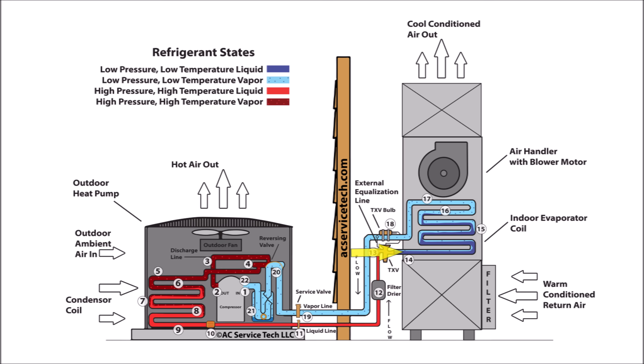At step fourteen, the liquid exits the metering device as a low pressure, low temperature liquid refrigerant. But this liquid rapidly expands into a mixture of 80% liquid and 20% vapor due to the lack of pressure and availability of space. The refrigerant then absorbs heat in the evaporator.